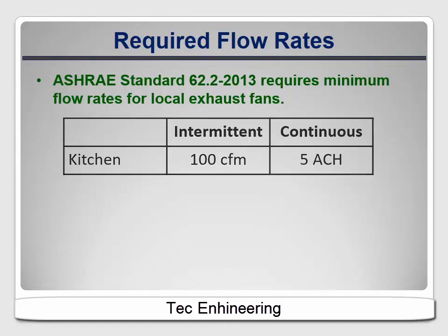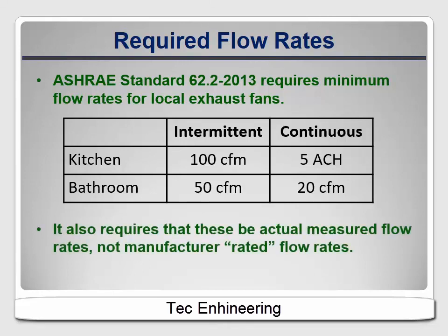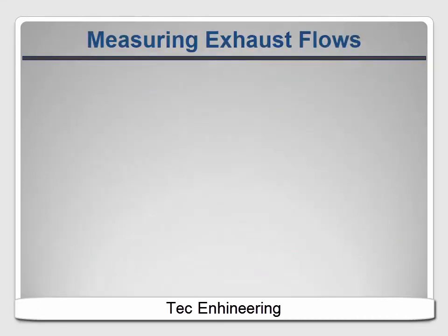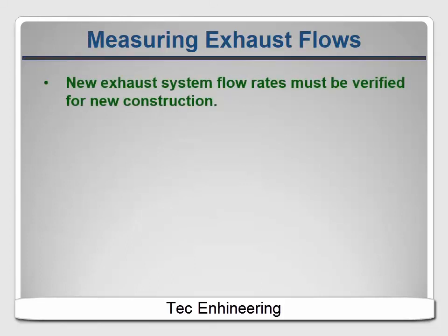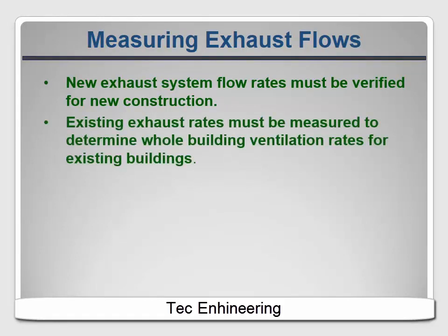For bathrooms, intermittent fans must provide at least 50 CFM; continuous systems must provide at least 20. The standard also includes another important requirement: these must be the actual measured system flow rates, not the manufacturer ratings for the fans, since delivered flow rates are often well below the rated flows. ASHRAE 62.2 requires measurement of exhaust system flow rates for numerous purposes. In new construction, testing is necessary to ensure that the installed systems meet the required rates. In existing buildings, the flow rates of the existing fans are used to determine how much mechanical ventilation is needed.